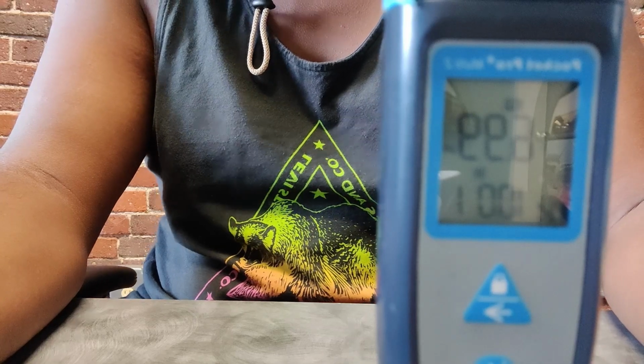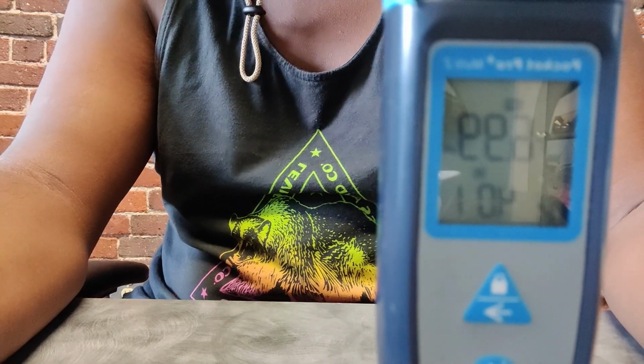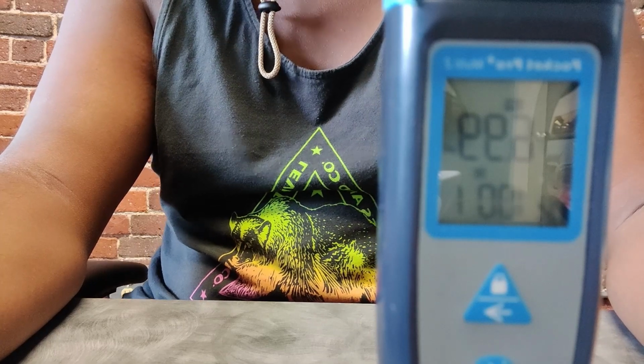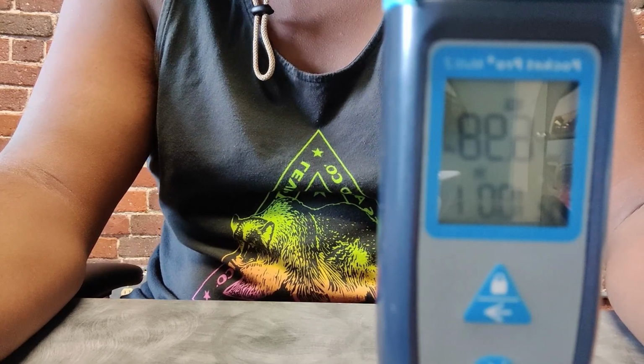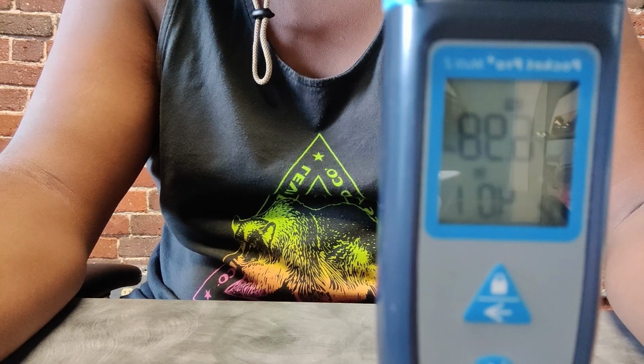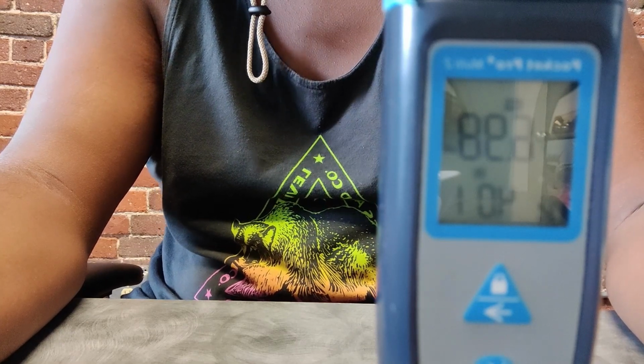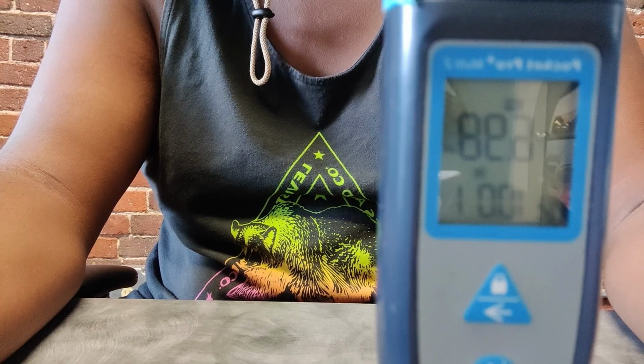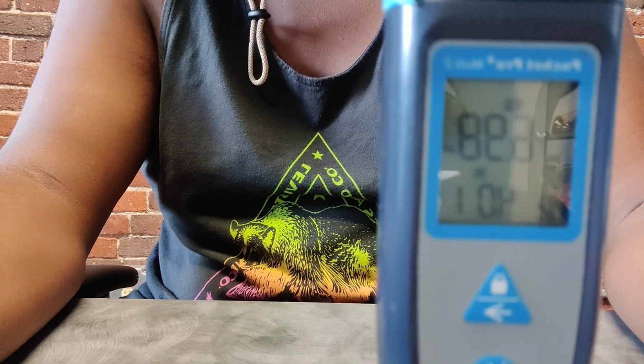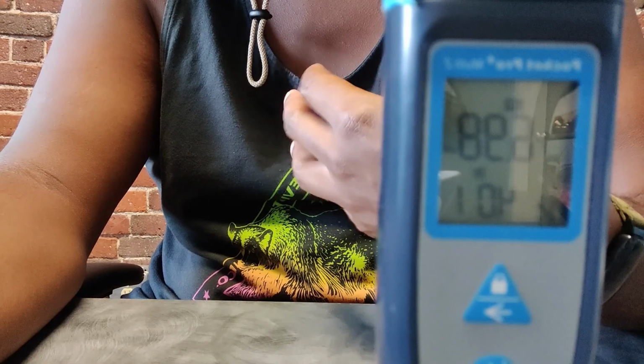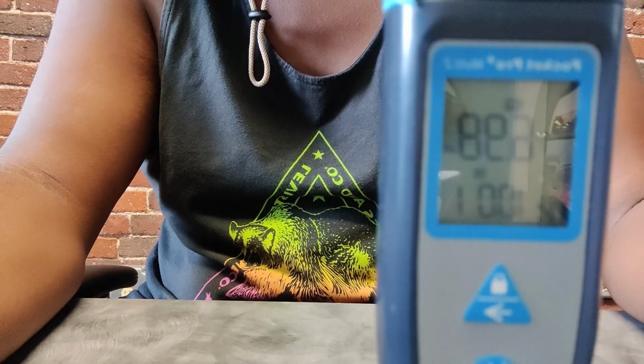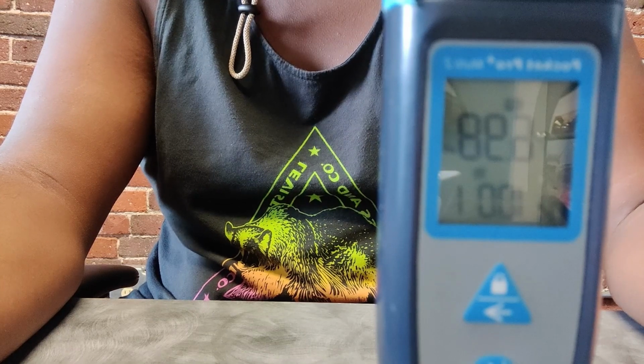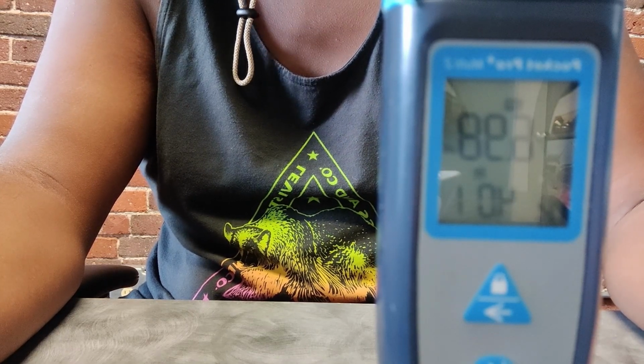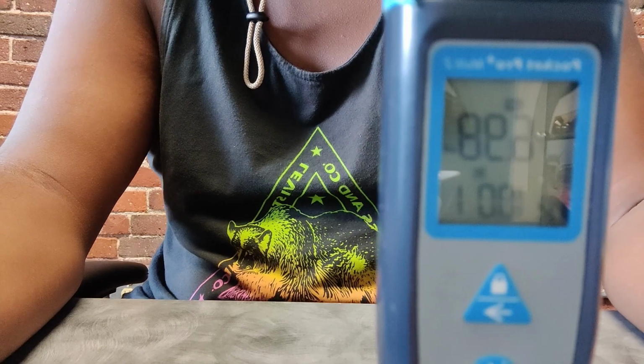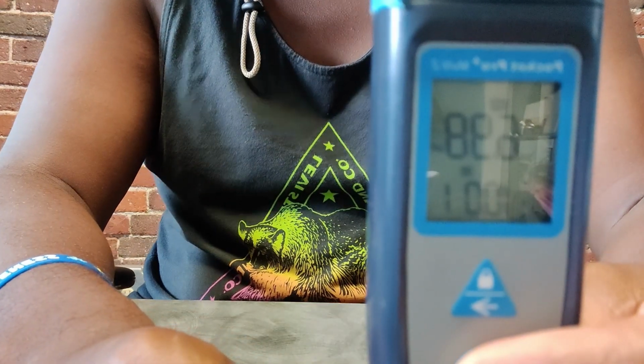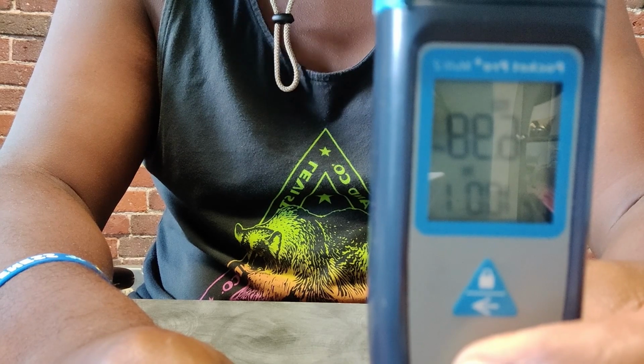Your bottom row is now going to flash between 4.01 and 10.01. The pH scale runs between 0 and 14. To calibrate water testing equipment for that range, there are 3 different standards that can be used: 7, 4, and 10. The Hach is capable of calibrating 4, 7, and 10, a 3-point calibration, but for our purposes testing freshwater rivers, we only need to calibrate 7, which is a 1-point calibration. The machine here is asking for either of the other 2 standards. We don't use them. So now you can press and hold the middle button. The screen will flash end, and the Hach will just accept 7.